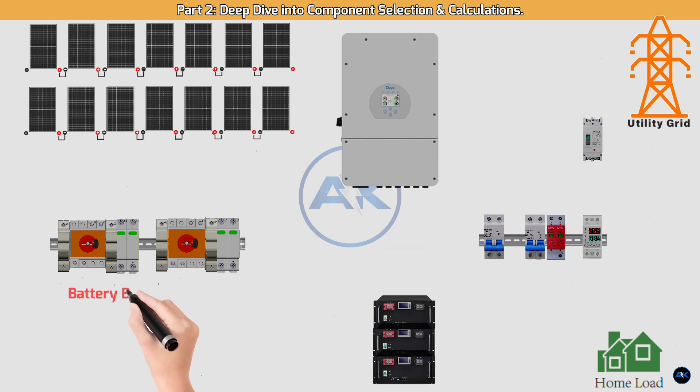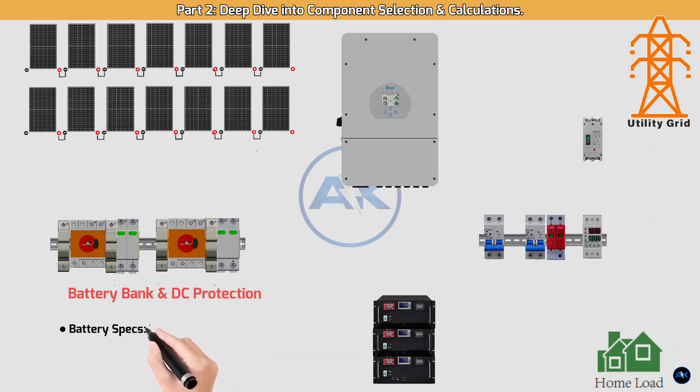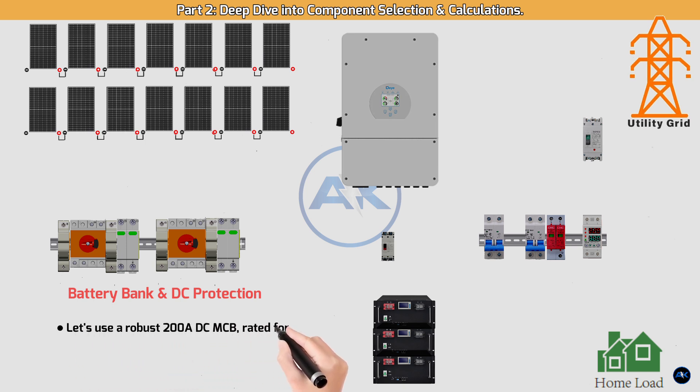Battery bank and DC protection. Battery specs: 3 × 5.12 kWh, 48V batteries. DC breaker for the battery: the Deye inverter can handle a substantial current from the batteries, so we'll use a robust 200A DC MCB rated for 48V. This breaker is placed directly after the battery bank and before the inverter — in an emergency, this is your primary disconnect for the batteries.